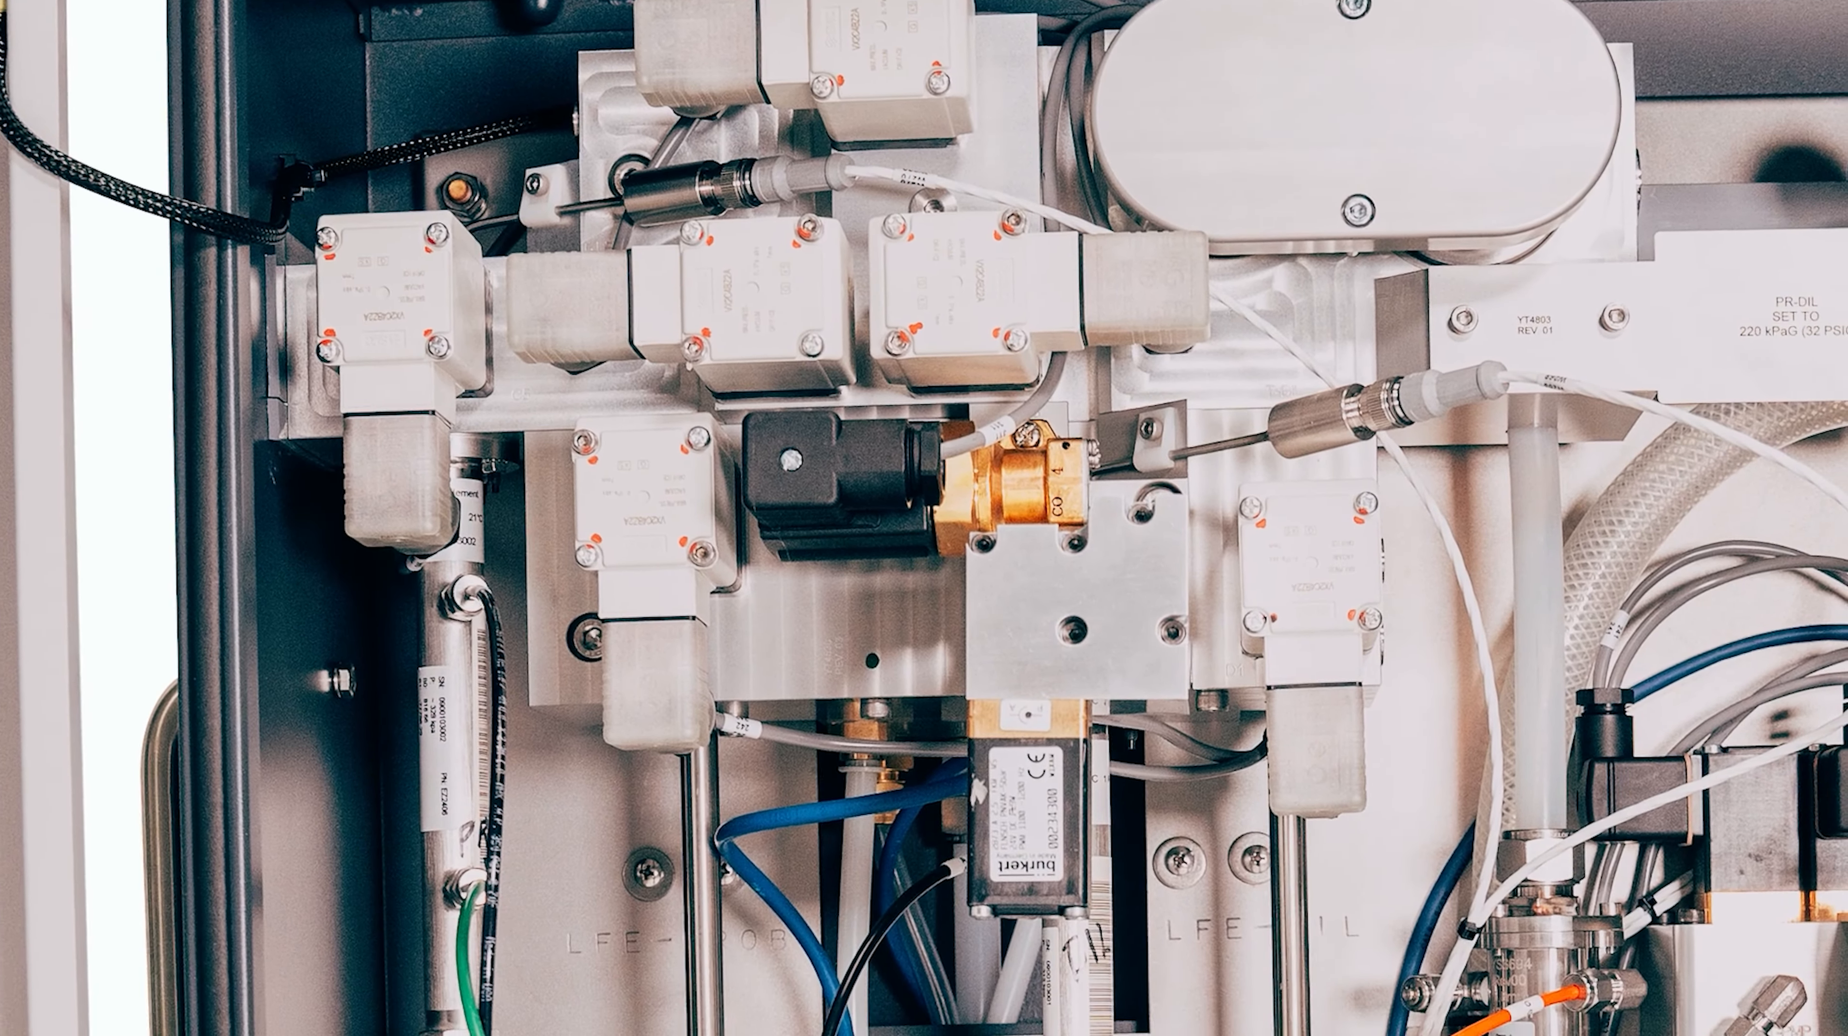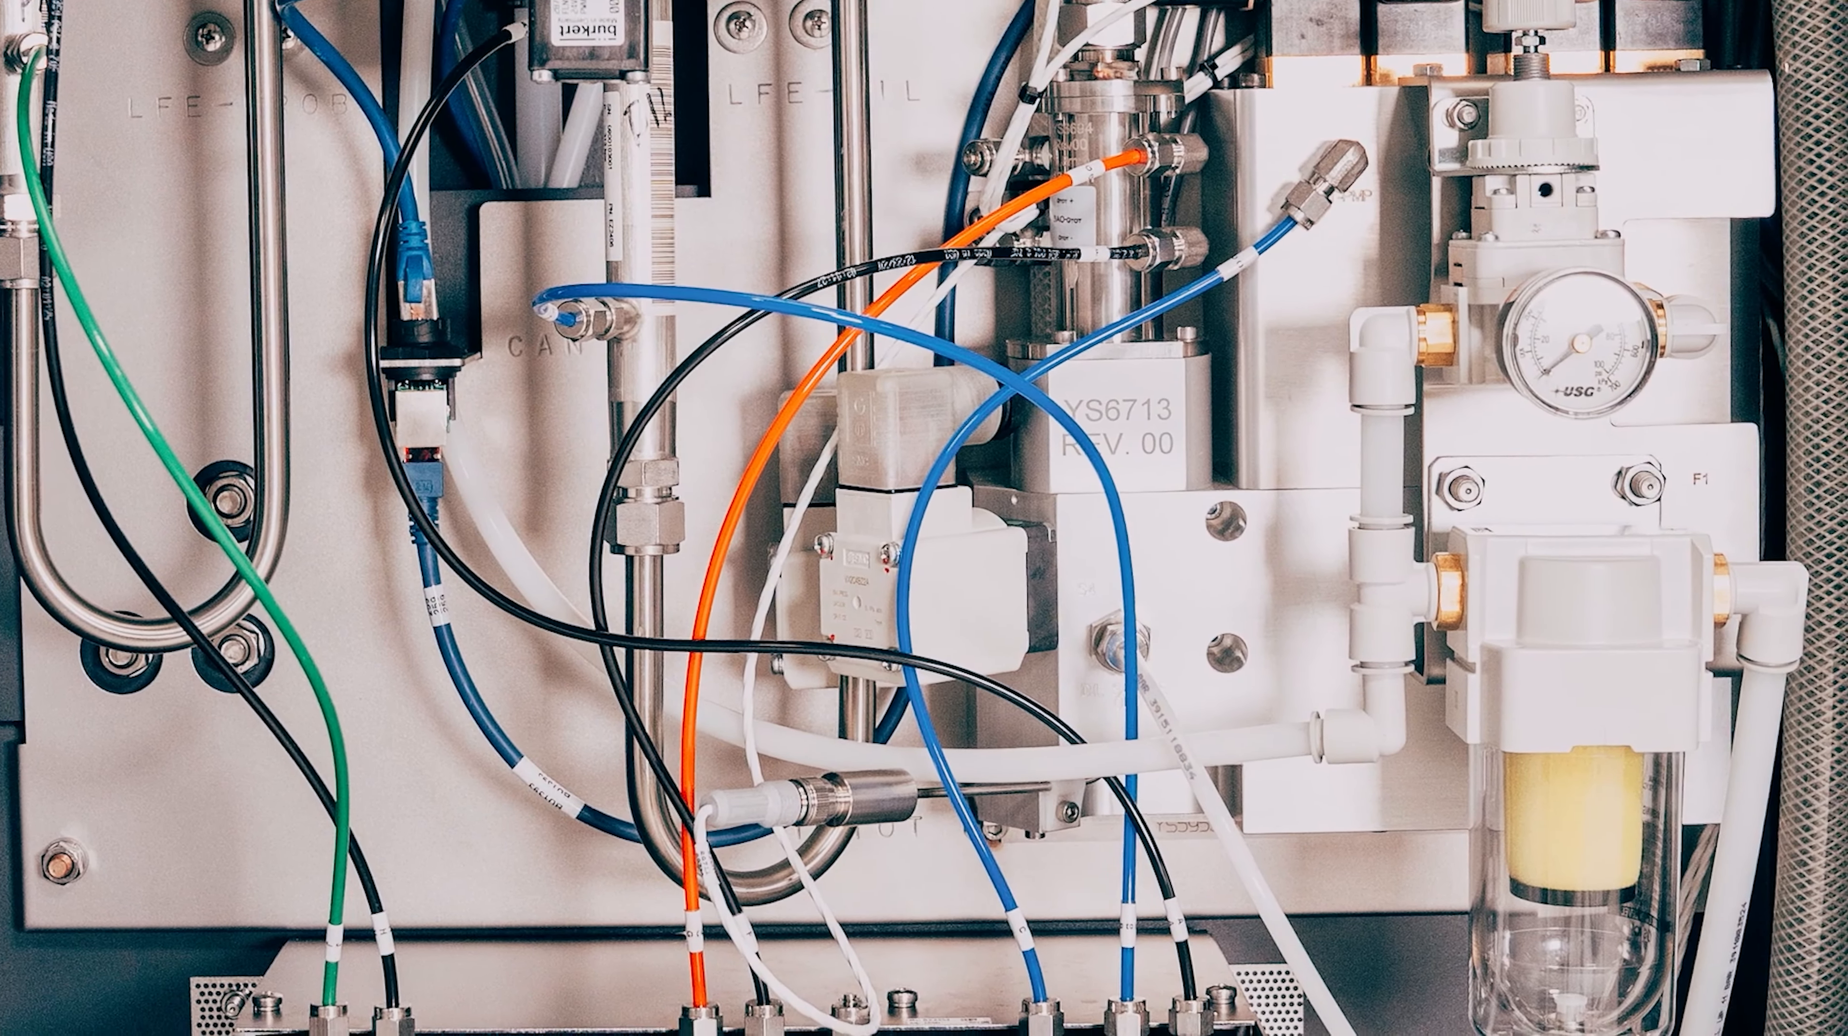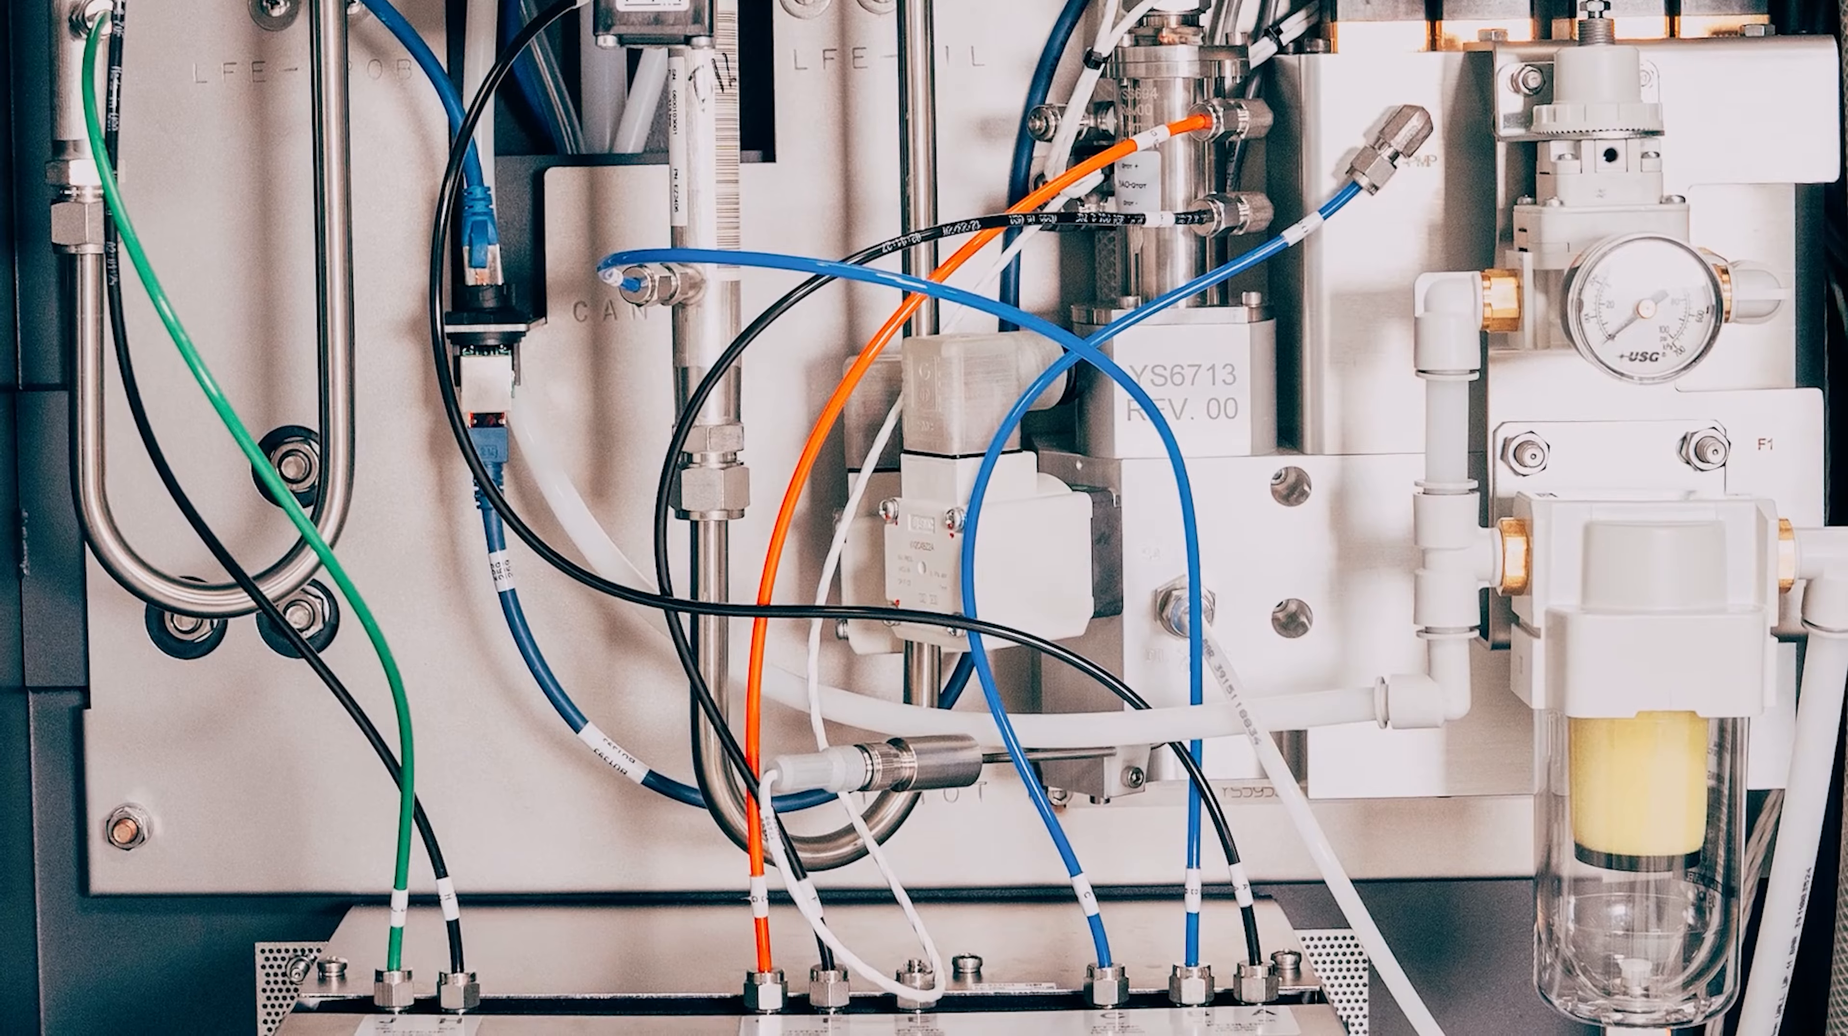So one of the big changes that we really did was on the control cabinet side. And if you look into this, one of the things we did was the pump module. The pump module is here and completely redesigned to avoid any false leaks by adding another valve, but also increasing the suction volume by adding a third Venturi module. That means we can now even have higher flows over several filters, plus also we are now fulfilling the altitude simulation requirements that some customers might have.